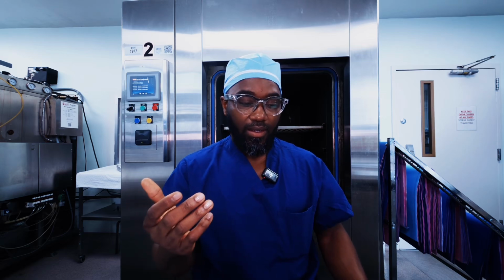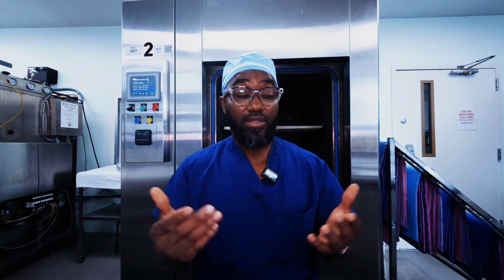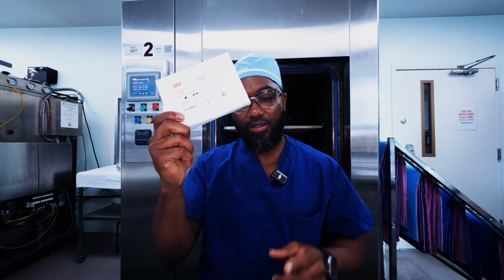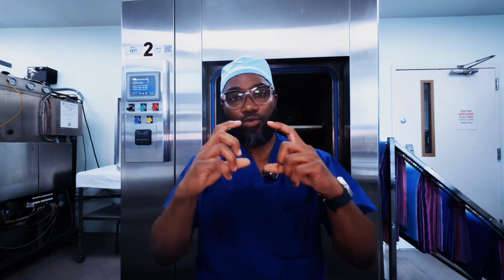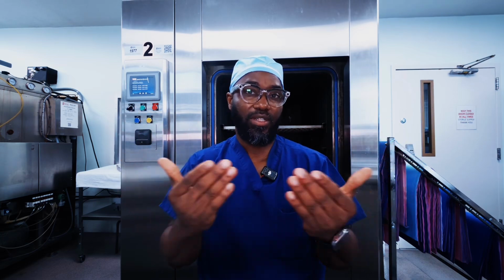The reason why it's important to check the efficacy of the sterilization cycle is that we do not guarantee sterility. One may ask, you go through all the process, why don't you guarantee sterility? We don't guarantee sterility because there might be soil still on the instruments that we sterilize that we didn't see. Or second, there might be a failed load. Even though your chemical indicator, biological indicator, and physical printout may pass, sometimes a tray within this load might be wrapped up too tight, which prevents the sterilant from entering the tray to render it sterile.